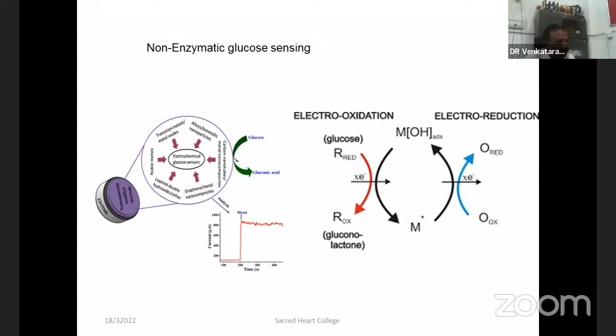And here, for example, if you look at the application of platinum, the solid line is the reaction of glucose on platinum, but this peak is not highly reproducible. One important parameter of a sensor for medical application is that your sensor should be accurate. Whenever you use a sensor, it should show the same value. Then only it can be applied for diagnostics, so that you can accurately diagnose the disease. But here, once it completes the cycle, if you come back to the second cycle, it almost becomes zero, because platinum is a material which oxidizes glucose into carbon monoxide and water. This carbon monoxide will strongly adsorb on the metal surface. So direct sensing of glucose at the metal surface is quite difficult.